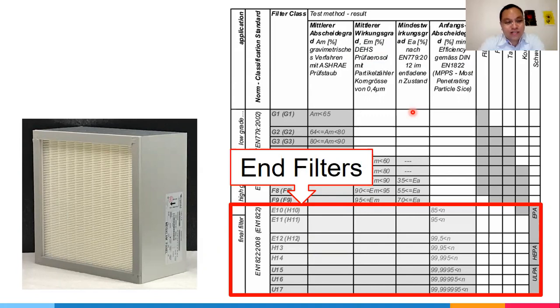Short answer, yes, it will cause high pressure. Actually, HEPA filters and ULPA filters have high pressure drops, around 200 to 250 Pascal. So if you're sizing your AHU, you should consider the pressure drop of your end filters, whether the filters are installed at your terminal unit or at the AHU.